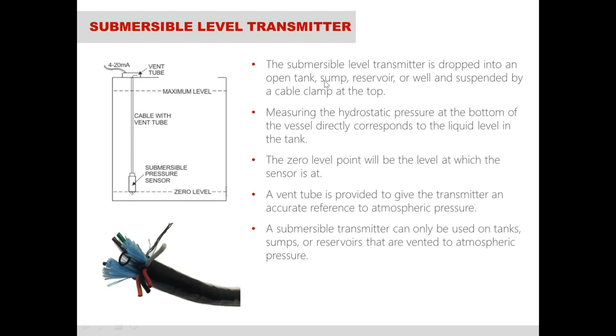Now, this submersible level transmitter only really works for vented tanks or vessels that are open to atmosphere. The reason for that is you need to have reference to the pressure on top of the liquid. That pressure is then pushing down on top of the liquid as well, and that can fluctuate the level measurement output.